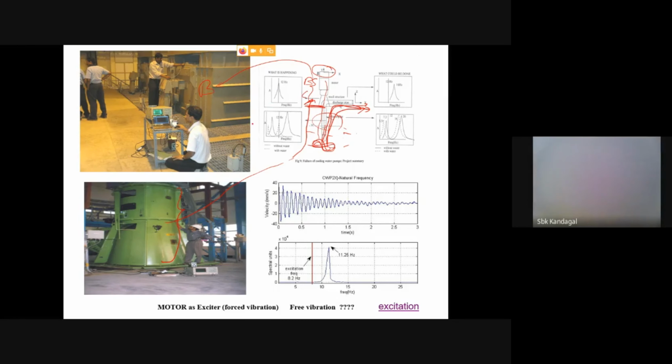The idea here is, whenever it is operating at something like 720 RPM, we can see there are a lot of resonance and vibration problems. We were supposed to find out the reasons why it has so much vibration, and then try to control that.